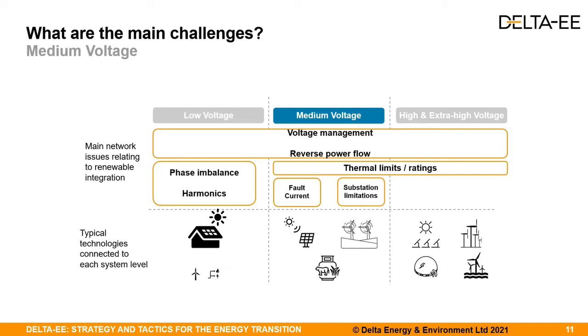Starting with wind and solar PV farms and their connections to the medium voltage network, we might again have reverse power flows, which may result in thermal ratings on some feeders being exceeded under scenarios of high renewable generation and low local demand. This is especially the case where line drop compensation for voltage is in place, which would make voltage management worse.